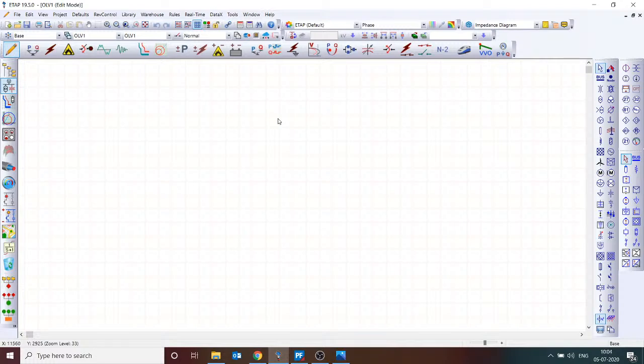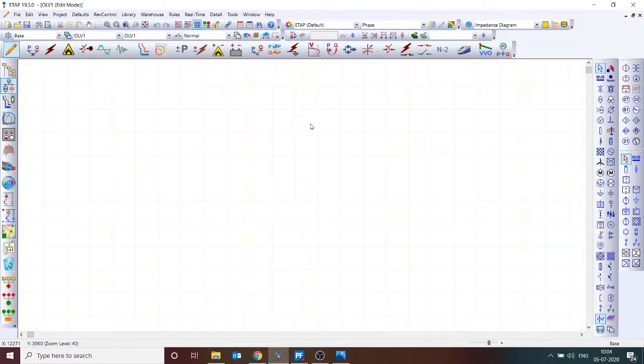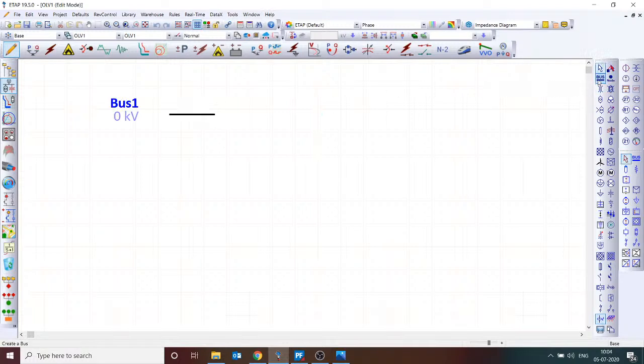So it is impractical to assume the slack bus or swing bus concept for load analysis across the full grid. We need to ask where this concept is applicable. The swing bus or slack bus concept is applicable where you have a very strong transmission system feeding a distribution system. Let me take an example of where the swing bus works and where it doesn't.